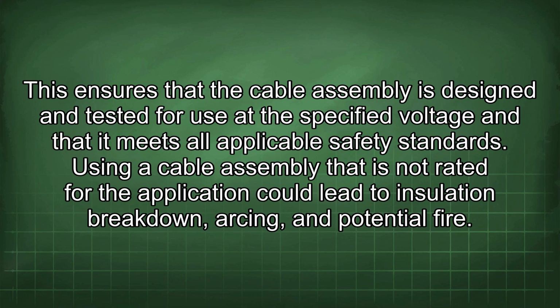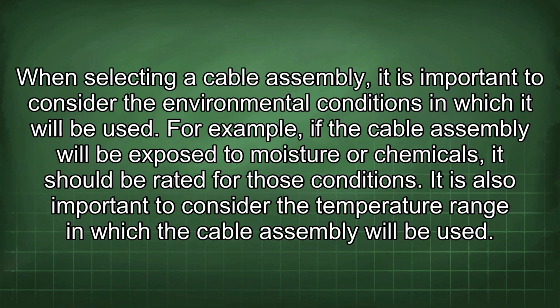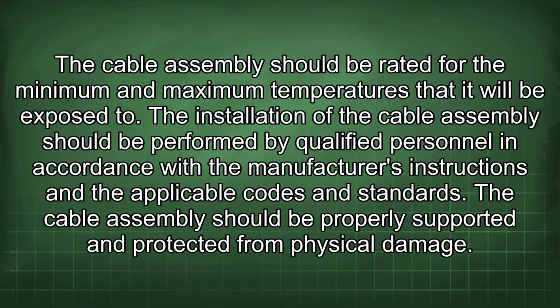When selecting a cable assembly, it is important to consider the environmental conditions in which it will be used. For example, if the cable assembly will be exposed to moisture or chemicals, it should be rated for those conditions. It is also important to consider the temperature range in which the cable assembly will be used. The cable assembly should be rated for the minimum and maximum temperatures that it will be exposed to.